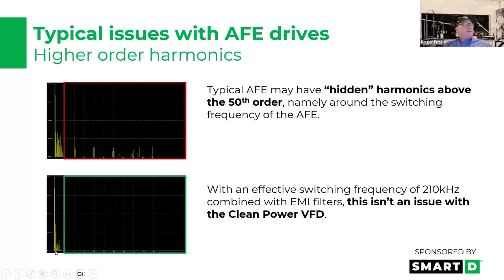But as you can see here, this is the order of the one with the Smart D, where the difference is that our switching frequencies are about 210 kilohertz. Most VFDs are running at 2.5 to 5, sometimes 7. So having that high frequency switching, plus our EMI filters that are built into the VFDs, we're able to clean this up all the way through the spectrum.